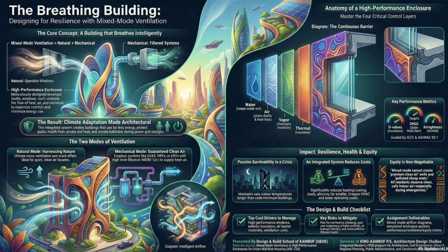Okay, and the second natural mode, which you see more in taller structures, is the stack effect. This is just basic thermal physics, right? It's pure physics. The stack effect is driven by temperature-induced buoyancy. Meaning hot air rises. Hot air rises. Warm air is lighter than cold air. So if you create a continuous vertical pathway, like a shaft or a stairwell, or even just the building envelope itself, and the air inside is warmer than the air outside, that warm air will rise. It gets exhausted through openings at the top, and that naturally pulls cooler replacement air in through openings at the bottom. So it's like a natural engine. It's a massive resource for energy-free cooling and ventilation. It's a powerful engine that works with no moving parts, just gravity and a temperature difference.